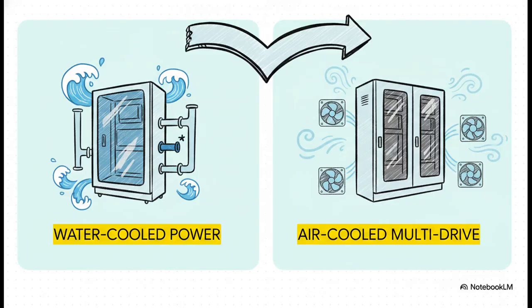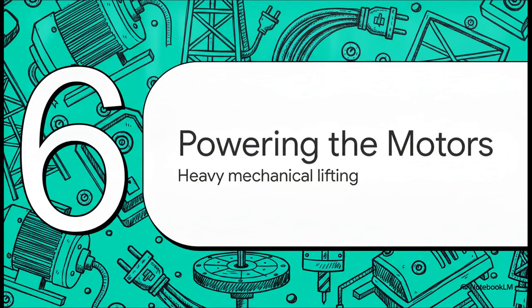It comes down to a pretty clear decision matrix based on your cooling setup and your electrical topology. If your vessel is committed to a water cooling loop, which is super common on drill ships or tight machinery spaces, and you need massive power, the ACS600W is your go-to. On the flip side, if your design leans into the multi-drive topology to save on cabling, and you want air cooling combined with that insane 25 microsecond precision of direct torque control, then the ACS800 multi-drive is exactly what goes into your spec.